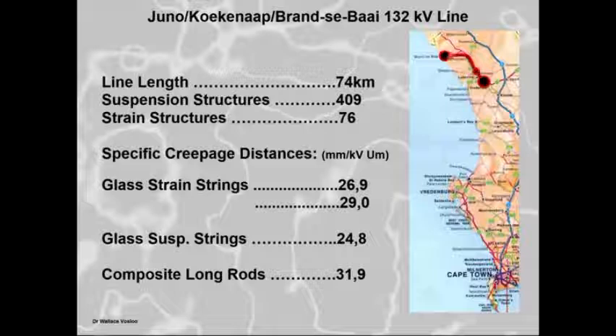Then from here onwards down towards the coast, we're running composite long rods at 32 millimeters per kV. Now, 32 millimeters per kV is beyond the 31 millimeters per kV, which is normally recommended for very heavy. And we also have experience that at 32 millimeters per kV, we can normally find in this type of region leakage currents below tens of milliamps. So we've got very good composite long rod insulators up there. We also have ones which are manufactured of a hydrophobicity transfer material. So it's a silicone rubber based composite with alternating open shed profiles. That's typically what we use along the coast, so that we don't get a lot of pollution catch. We have an open, aerodynamic and alternating shed profile. So we optimize the profile and we've got good creepage distance with a hydrophobicity transfer material. So we're not really expecting pollution flashover here.